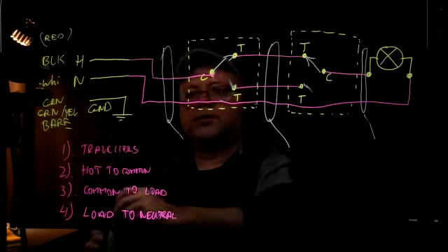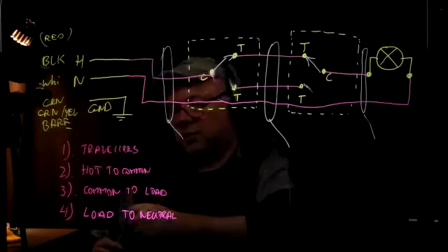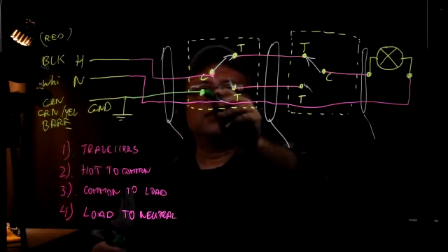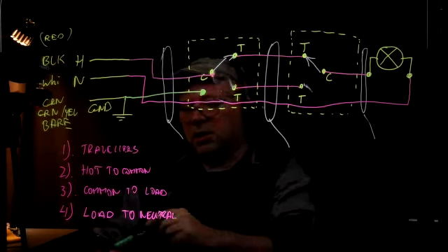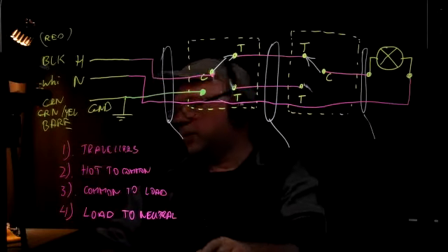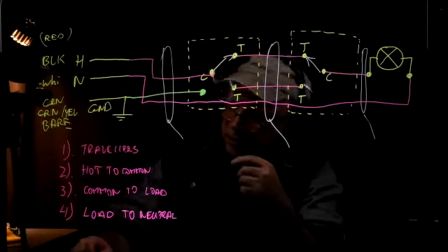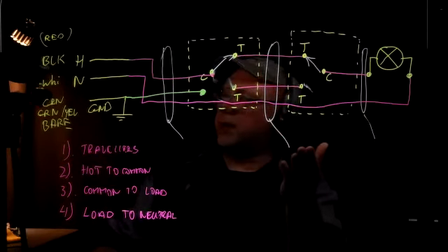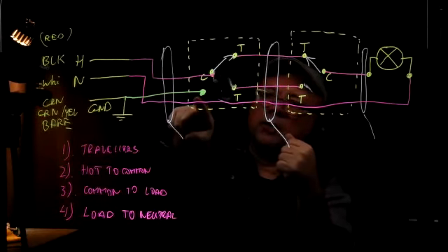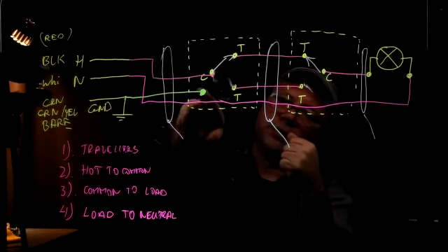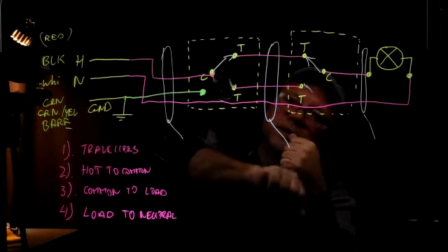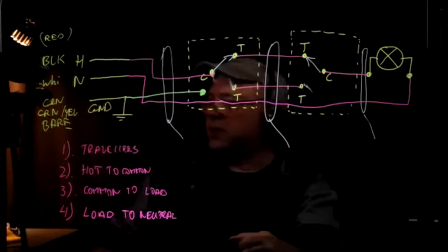Now, of course, this bonding wire is going to have to be connected to the bonding terminal in the device box right here. If it's an EMT type of raceway, then all you have to do is connect that bonding wire or grounding wire to the box, and the bonding or grounding will continue through the metal structure of the EMT, or electrical metallic tubing.